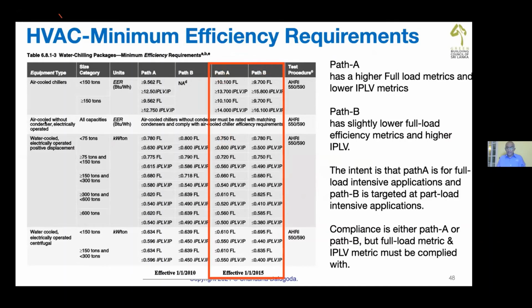Path A, Path B is a different scenario. Path A comes as the full load intensive applications, Path B for part load intensive applications. So that's how we select chillers, equipment for green building. So why I emphasize this: our own green practitioners have to be very careful. You'll have to do a real selection and provide proof for rating. You can't just say we have a building model and we have a 30%, 40% saving on the model. No, we've got to show your actual building has equipment complying with 90.1. So this is how you select chillers.